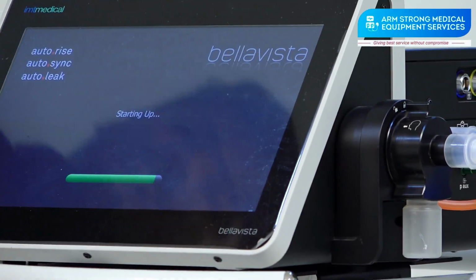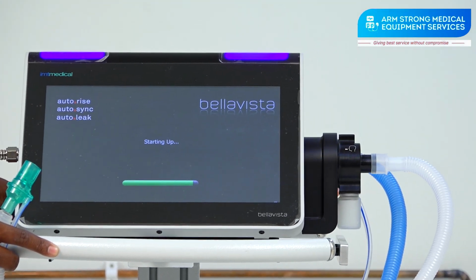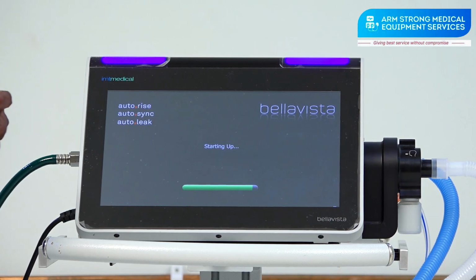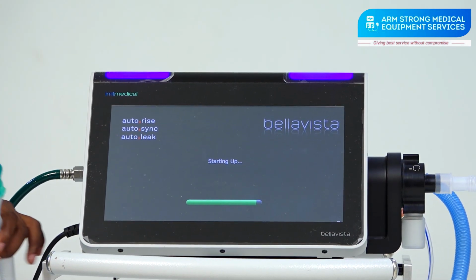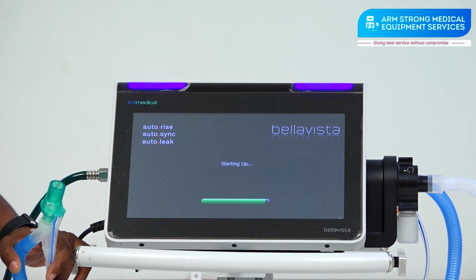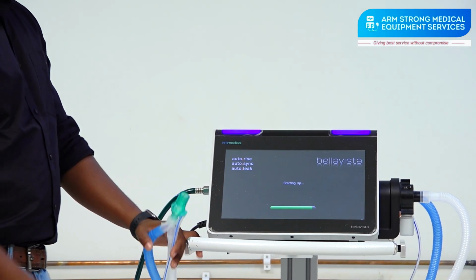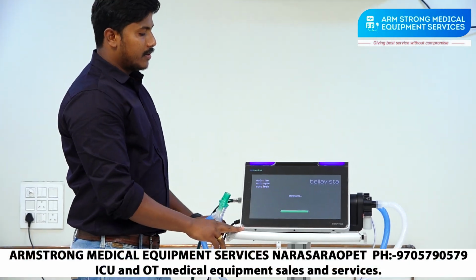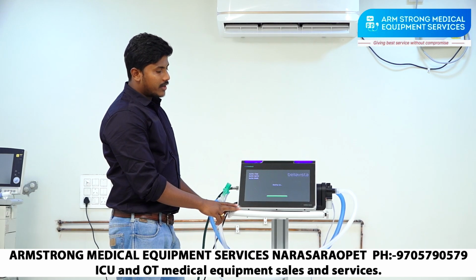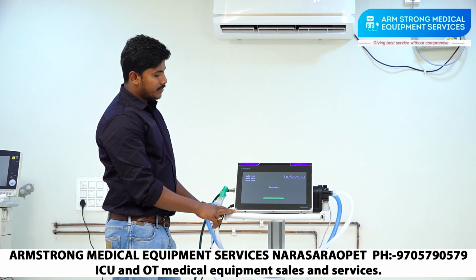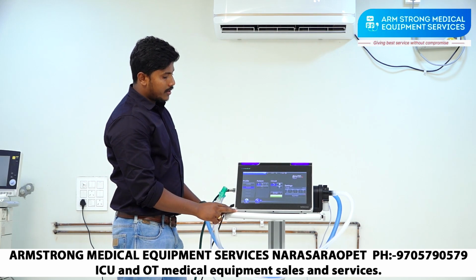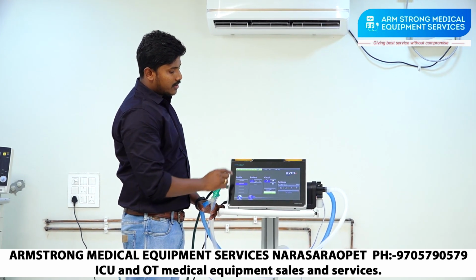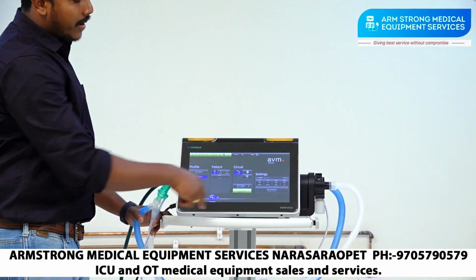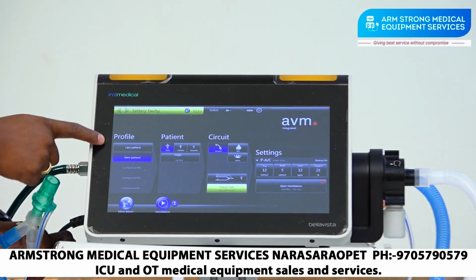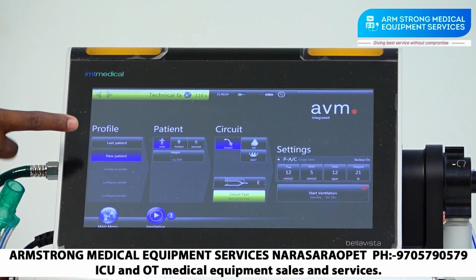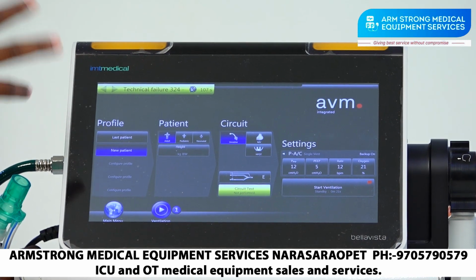Now the ventilator has auto rise, auto sync and auto leak compensation, BELLAVISTA 1000. This ventilator is made in Switzerland. Now it is starting up. The self test of this ventilator takes approximately 2 minutes. So this is the startup screen. After switching on the ventilator, the startup screen will come like this, and here you see profile. Profile, last patient means a previous patient who was connected already. All those modes and settings will come.